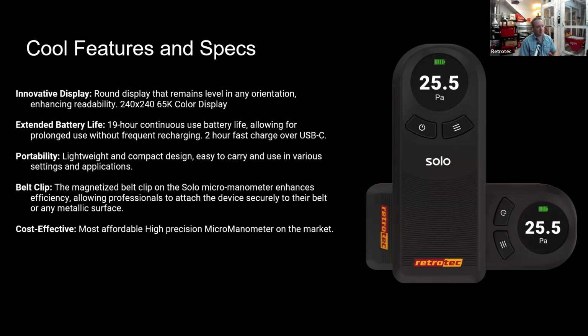So even if you don't have a blower door, or any idea about the condition of the building envelope, you can start turning on exhaust fans and things like that to see if that moves. You can do that with this gauge just to get a ballpark idea of if the house is leaky or tight, and start to understand what a tight or loose building envelope looks like when you start changing things around in the house.